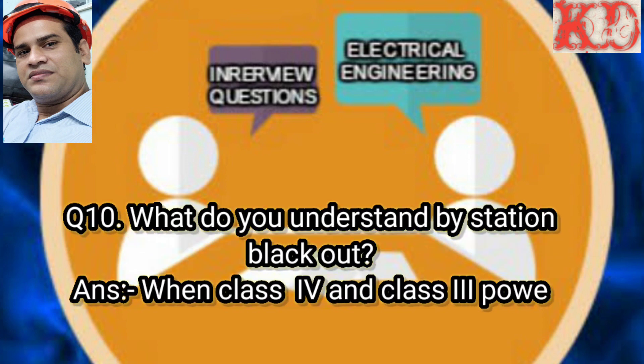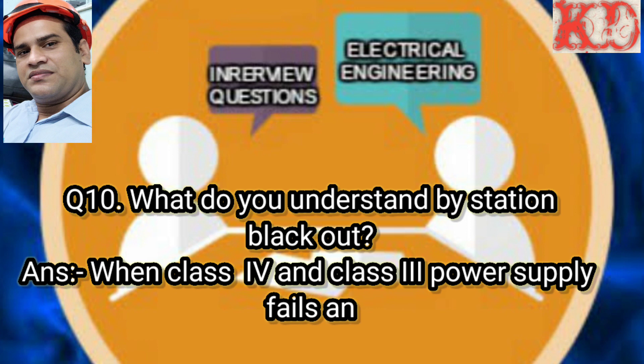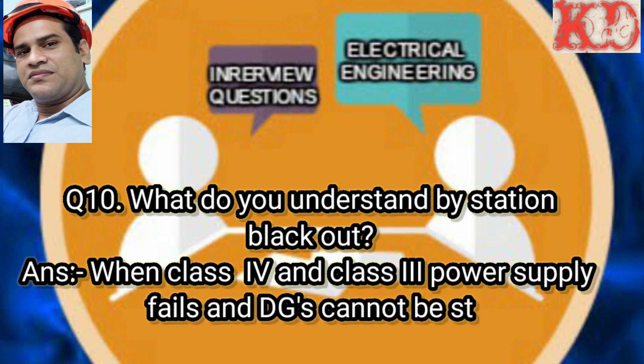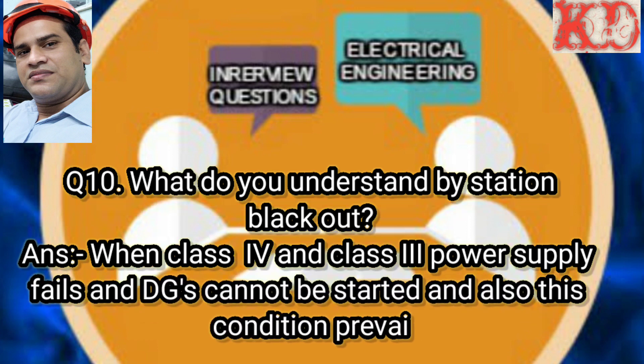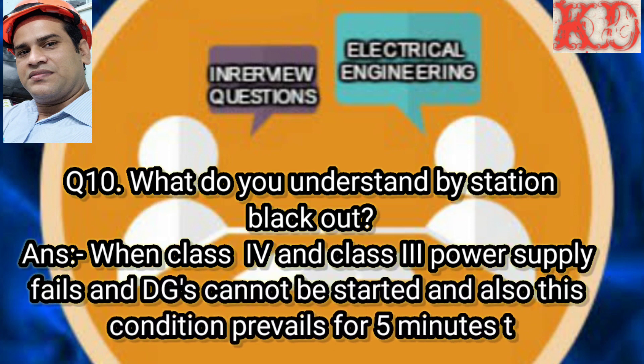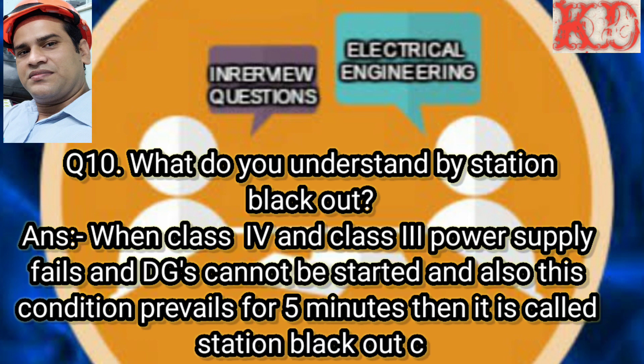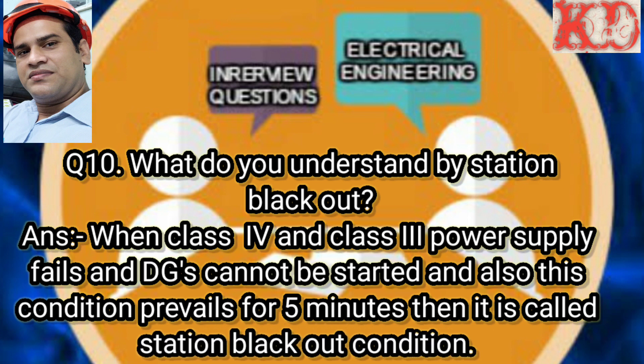Question number 10: What do you understand by a station blackout? Answer: When class 4 and class 3 power supply fails and diesel generators cannot be started, and this condition prevails for five minutes, then it is called a station blackout condition.